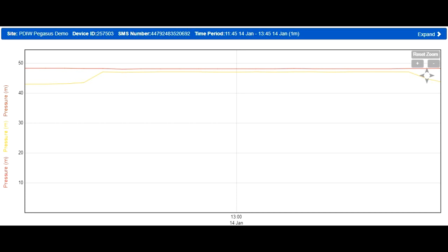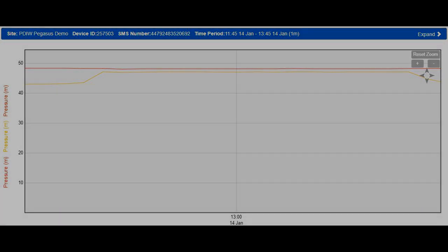By the simple action of letting that water go out of the PRV's upper chamber, we can see now that the head loss that previously was between 5 to 6 meters, now is less than 1 meter. So, we know for sure that we were able to recover about 4 to 5 meters and put that pressure into the network, improving the quality of service for that DMA.